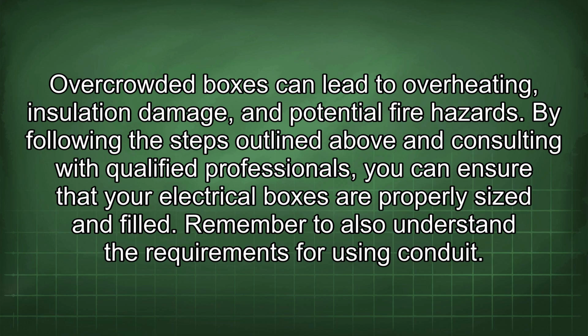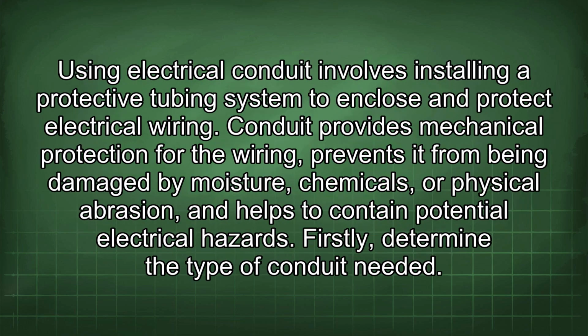By following the steps outlined above and consulting with qualified professionals, you can ensure that your electrical boxes are properly sized and filled. Remember to also understand the requirements for using conduit. Using electrical conduit involves installing a protective tubing system to enclose and protect electrical wiring. Conduit provides mechanical protection for the wiring, prevents it from being damaged by moisture, chemicals, or physical abrasion, and helps to contain potential electrical hazards.